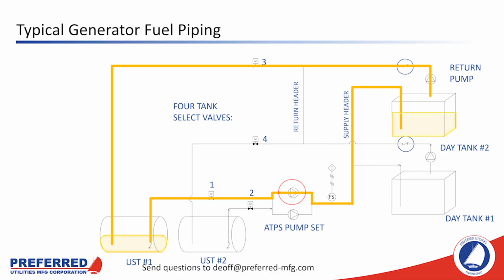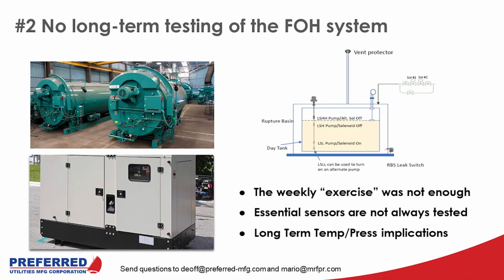Number two on my list were end users that were experiencing pressure and temperature swings in their fuel oil system. Given some of these auxiliary generation components are only tested for a brief period of time, sometimes not all end users have a chance to do long-term testing. When I say long-term, I'm talking about days and weeks. So when you have all these components, and I'm referring to boilers and auxiliary generators, operating at the same time for many hours and days and weeks, you start running into some temperature and pressure swings if your system is not adequately designed. One example is the day tank fuel overheating.